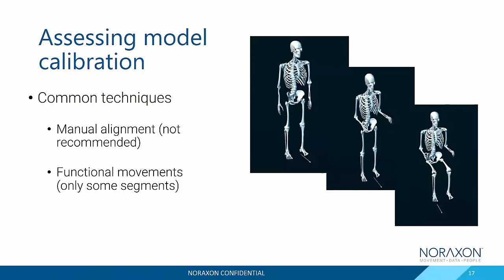There are some functional movements you can do, functional calibration. This is where you try and detect where the bones are by using some sort of assumed movement. And this can work, but it's only really valid for certain parts of the body. So what most IMU systems are doing is providing a static pose type calibration, and this is what we're seeing on the right here. Different poses which put you in assumed positions, usually sort of neutral or 90 degrees of flexion type of positions. And these are assumed positions that we're not measuring how you're sitting, but more controlling it.